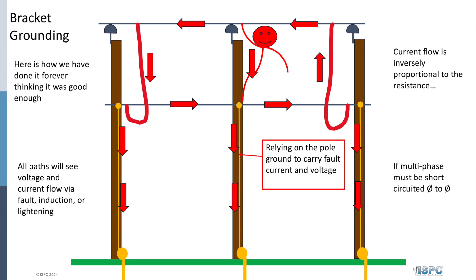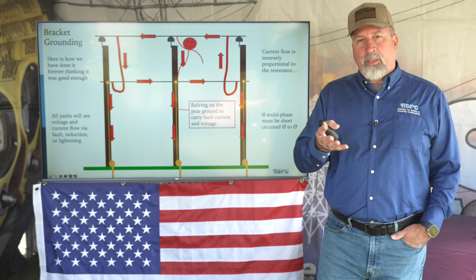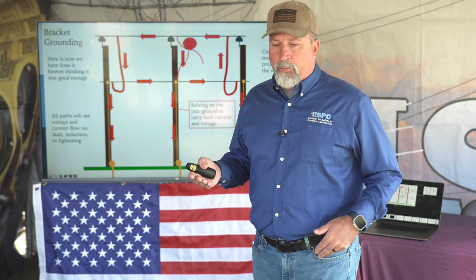In an incident, that's probably not going to be good enough for you, right? So now we're required, where reasonably possible, to install our grounding in an equipotential fashion. Now, this is all assuming that all your conductors are intact. Obviously, if you have broken neutral or broken phase wires, those type of things, you're going to need to install some bracket grounding until you get to certain points.